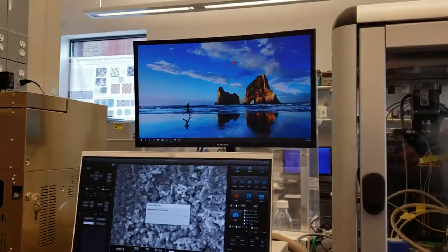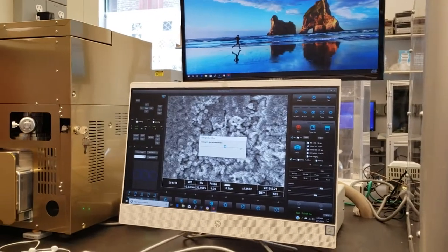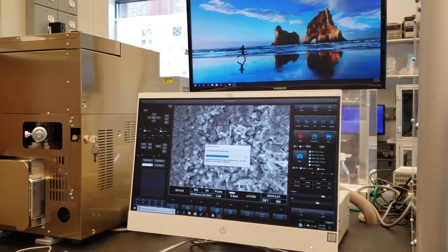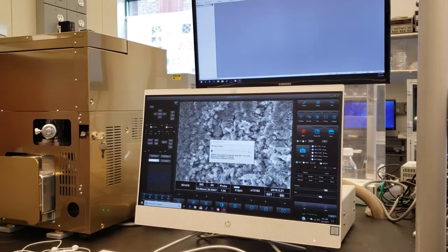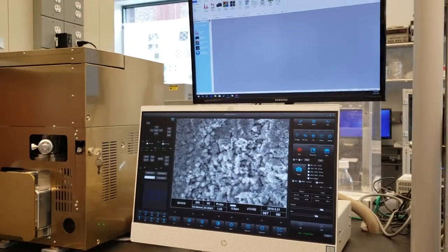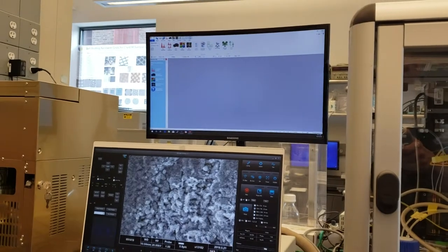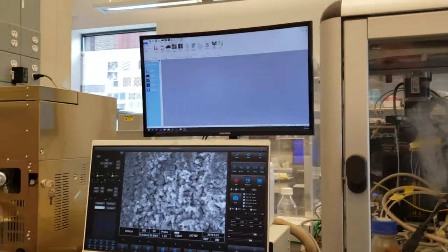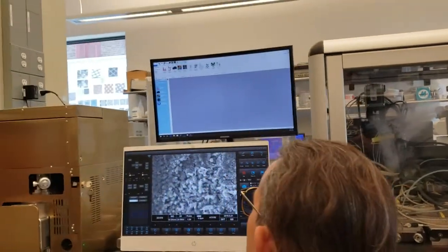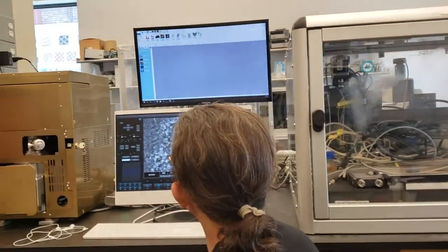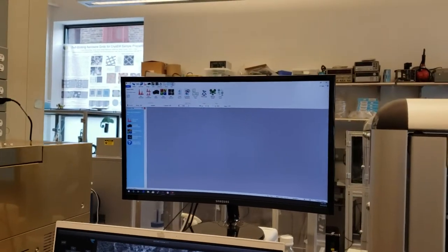I'm just going to double click Iridium Ultra. As soon as I double click, it opens this loading screen, it's initializing, communicating with the analysis dongle. All this stuff, you want no errors to come up during that initialization. Eventually it pops open the software bundle. This up here is our main software window, and as you can see, right now we have X-ray events up here. If we look at this little top bar, see what it says, C/S? That stands for counts per second, or X-ray events per second. So right now we have roughly 200 X-ray events per second.